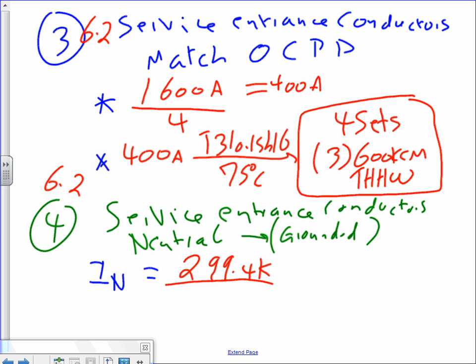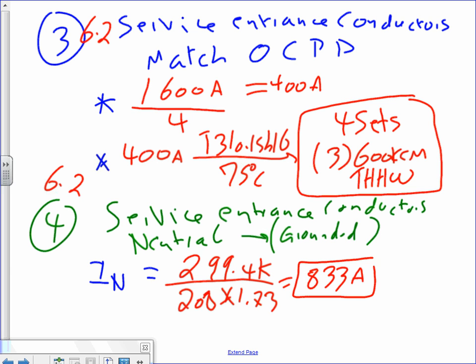Okay, divide this by what? 208 times 1.73. Anybody know why? Because the neutral load will be balanced between the 3 phases, right? When you guys do this math, you're going to get closer to this number. 833 amps. 833 amps. That's your amps for the neutral. Okay? So that's my amps for neutral.